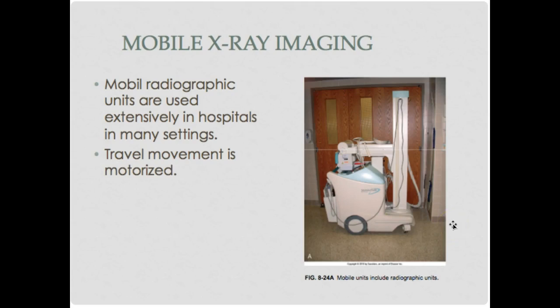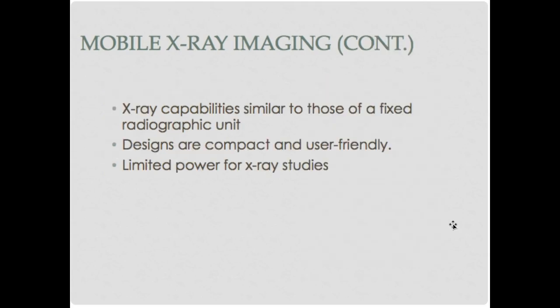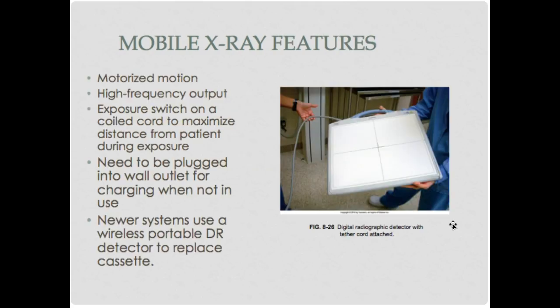Mobile x-ray units are used all over the hospital. They are motorized, very heavy, and compact with user-friendly designs. Make sure you have enough power before you leave — check your battery. The units weigh a few thousand pounds and you won't be able to move them without power. We have an exposure cord so you can stand as far away as possible when taking the exposure. Many are moving to DR plate technology and wireless battery systems — always bring a backup battery so you don't run out during your portable runs.